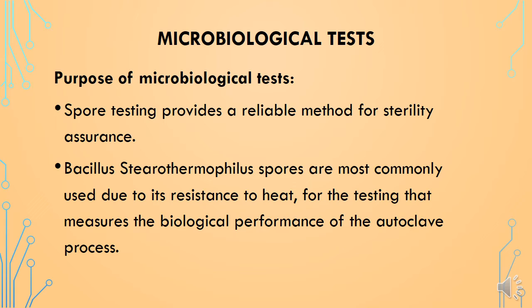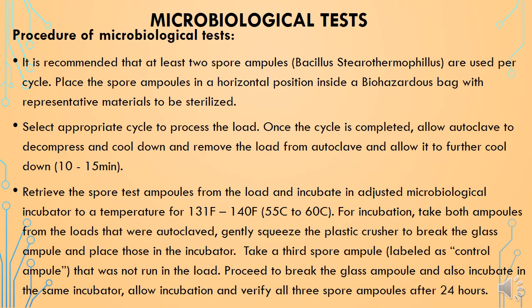The next important qualification test is the microbiological test. This test is done to get sterility assurance for sterilization processes done by the autoclave. Spore testing provides a reliable method for sterility assurance. Bacillus stearothermophilus spores are most commonly used due to their resistance to heat. It is recommended that at least two spore ampoules of Bacillus stearothermophilus are used per cycle. Place the spore ampoules in a horizontal position inside a biohazardous bag with the representative materials to be sterilized. Select the appropriate cycle to process the load.